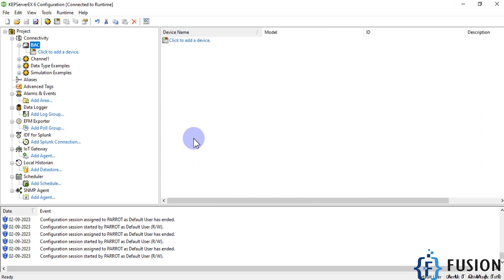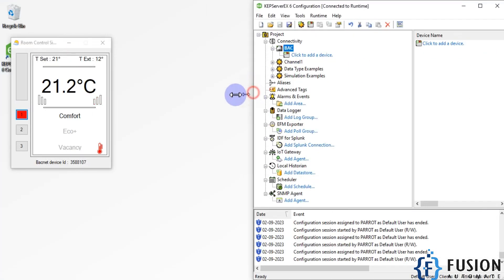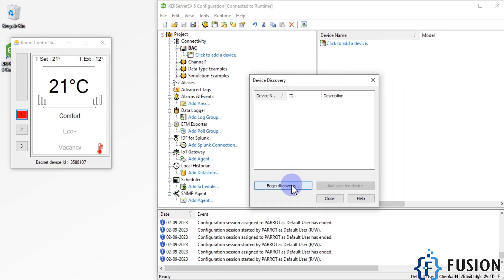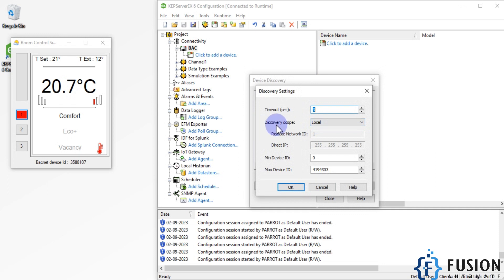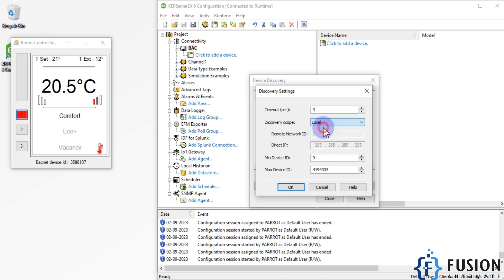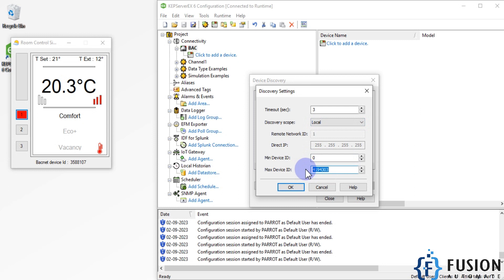Now we want to auto-browse the device rather than adding it manually. Right-click and select Device Discovery, then press Begin Discovery. You can choose the discovery scope: local, global, remote, or direct IP. With direct IP you specify the device's IP address. If the device is a simulator or is on the same network as your system, choose Local and click OK. You can also set the minimum and maximum device ID limits.